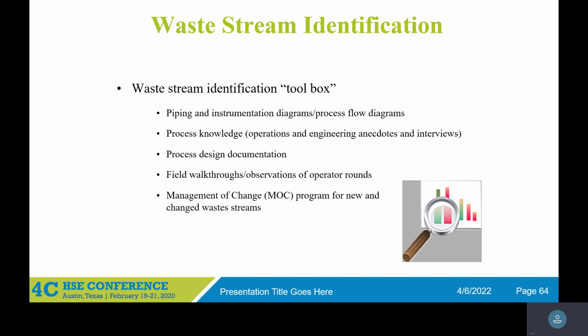So when we do a program, we have what's called a BWON doc, the documentation and compliance tool. It's a complex spreadsheet, but it still is a spreadsheet, right? But you document everything. You have every single waste stream and how you arrive at those conclusions, that here's the waste, and this is how we arrived at the waste. We got it from such and such mass balance, or we did a stopwatch, or we talked to operations, or we followed around. This is what we believe is the waste quantity, and this is the highest it has been for the last 5 years.